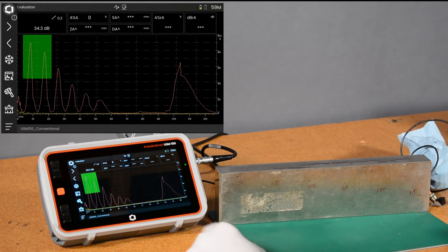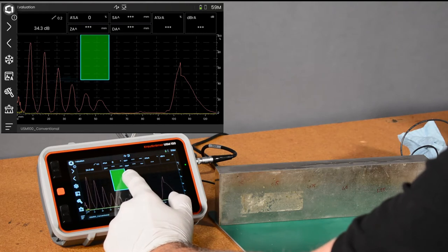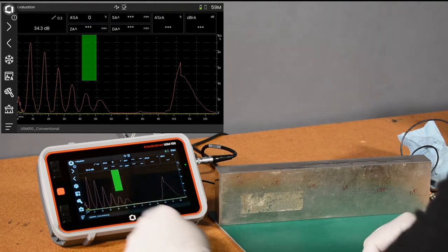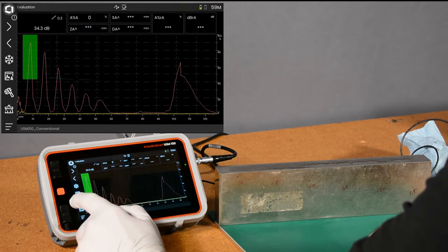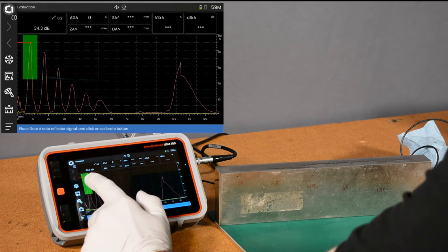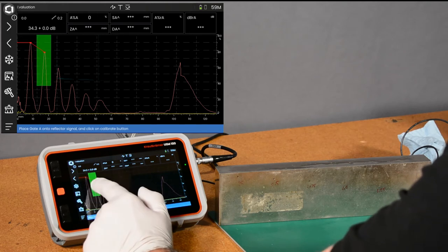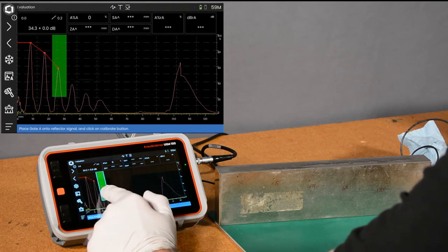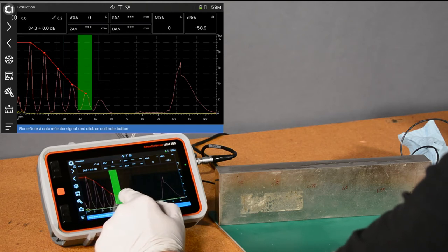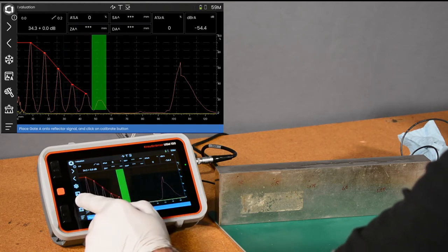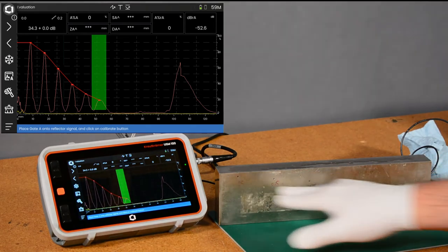Okay. So now that I've gotten all those peaks recorded, let me move my gate out here and make it just a little bit narrower. Now what I'm going to do is move to my first hole and hit my calibrate. You see I've begun drawing the DAC curve on the screen, and now I can just go from point to point: calibrate, calibrate, calibrate, calibrate, calibrate.